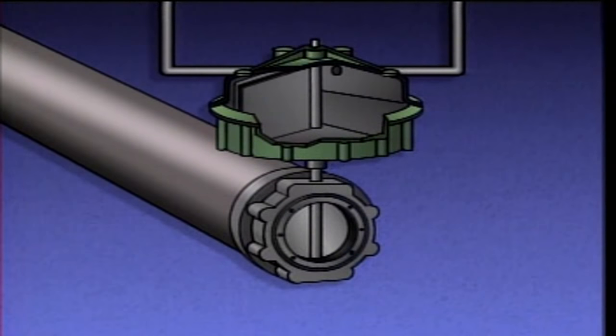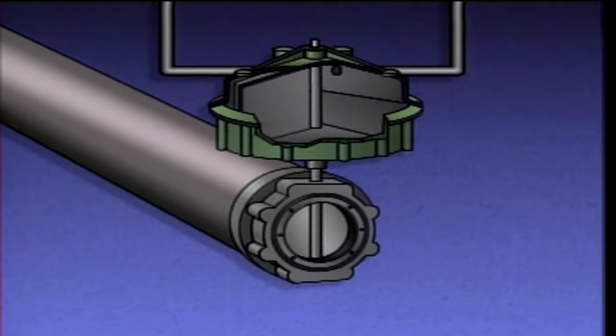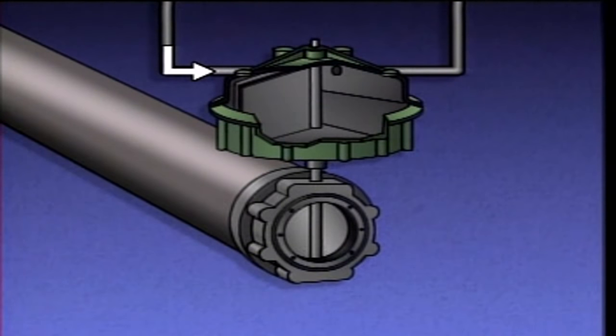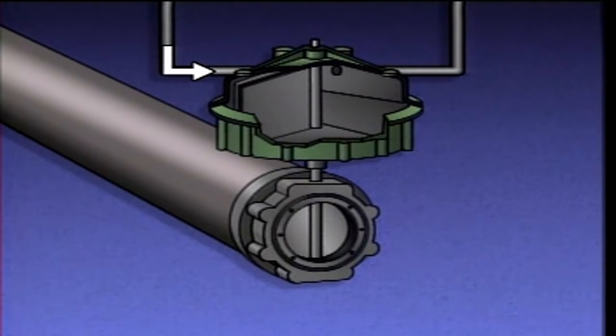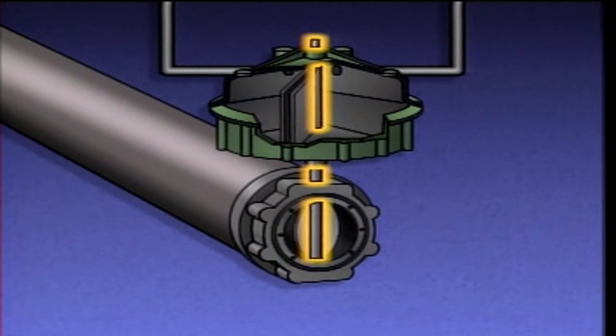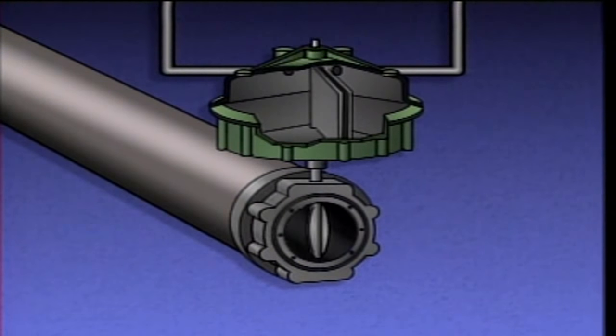In a cutaway of a vane actuator operating a butterfly valve, when air pressure is supplied through the air supply port, it pushes against a vane, causing the vane to swing across a housing. This turns a shaft, and as the shaft turns, it opens the valve.